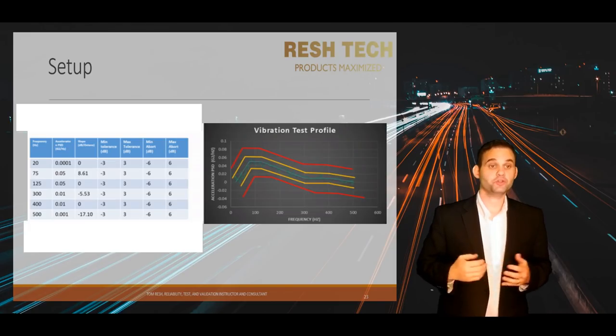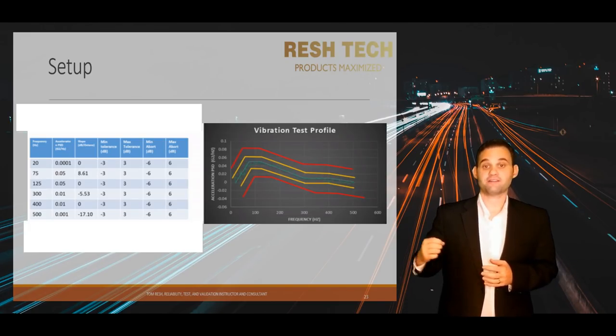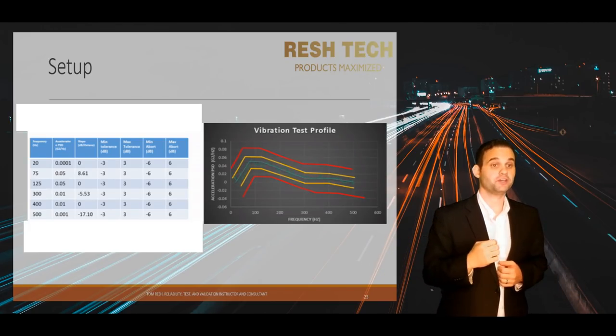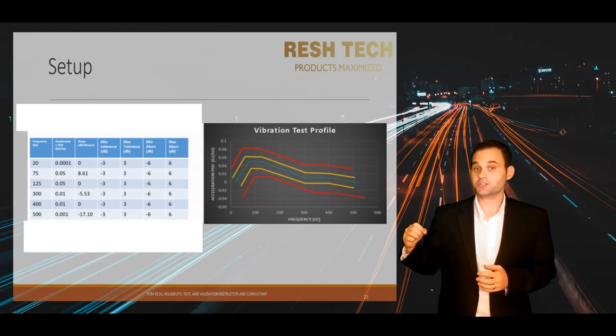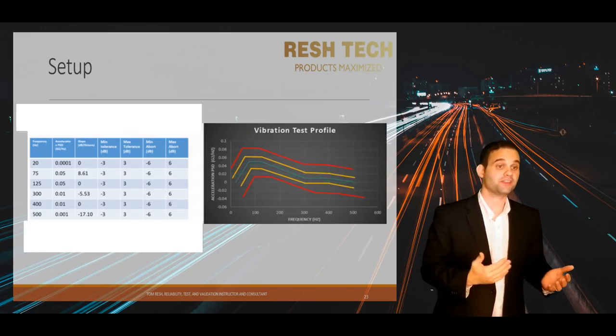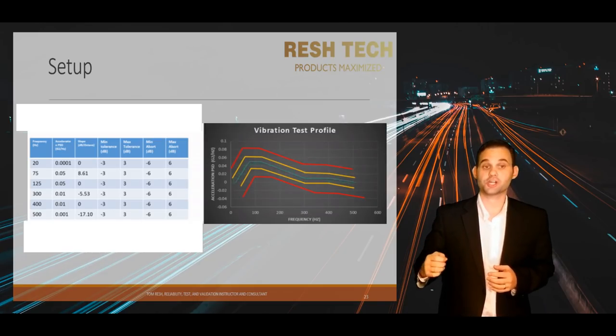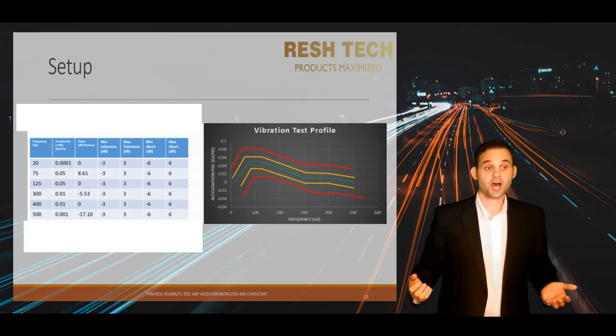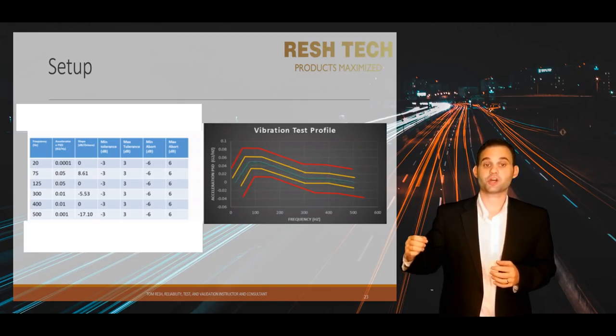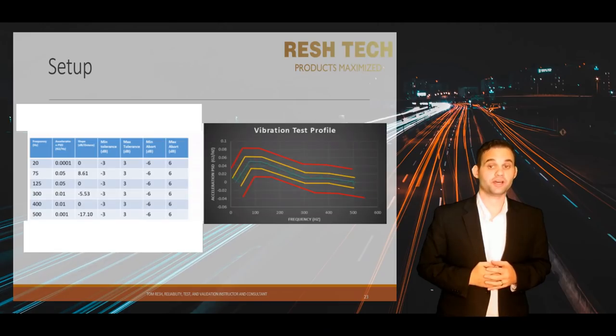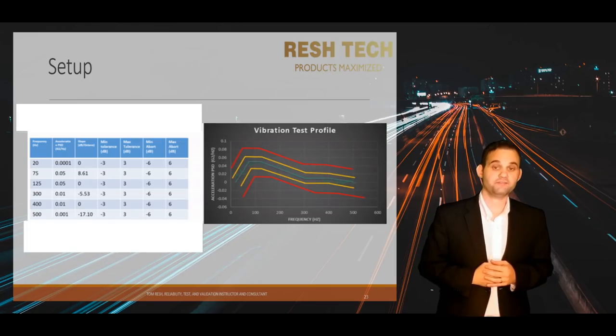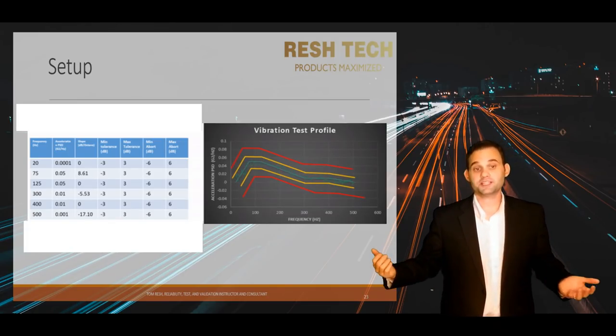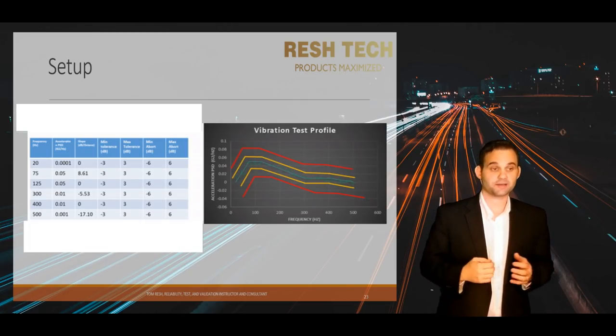In your test profile menu, you can either enter the slopes and frequencies — which will auto-calculate your acceleration at a given frequency — or enter your acceleration and frequency and the controller will auto-calculate the slope. You typically don't have to enter both values manually. The tolerance or limits for min and max are your test tolerances for your control line. Depending on your specs, a deviation of the control line will result in a failed test, but depending on your product, you may not care about this limit.